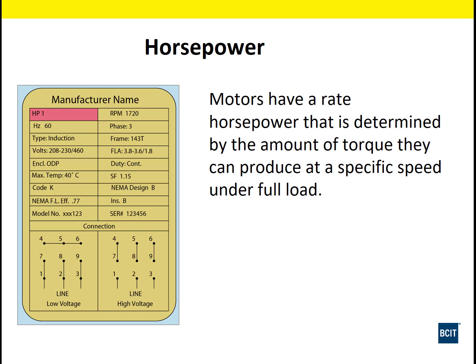So first thing we look at is the horsepower. Horsepower is the amount of work that the motor can do. This is typically matched to a specific amount of torque that the motor is going to be turning. So we size our motors to the equipment that it's going to power. This 1 horsepower motor here is going to be sized to a certain amount of foot-pounds of torque that the equipment it's connected to will require to operate.